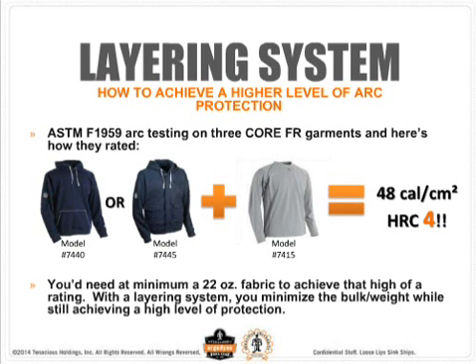At Ergodyne, we have conducted ASTM F1959 ARC testing on a few of our garments in our core performance workwear FR line, and here's how they rated. It's kind of amazing. The sweatshirts, models 7440 and 7445, by themselves rate as an 18 cal, and the model 7415 rates as a 7 cal. If you were to do simple math, you would think it would be a little over an HRC 3. But in actuality, this goes to prove how important those air gaps are in protection. When you wear it as a system, it actually protects you up to a 48 cal, so you receive an HRC level of 4.